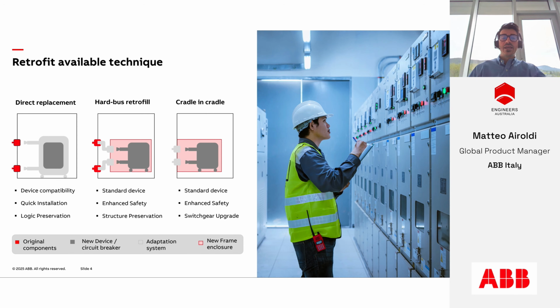The third technique is cradle in cradle. This technique introduces a new frame enclosure inside the cell, allowing the installation of a modern breaker. While it's a valid option for low voltage systems, it is not commonly used for medium voltage applications due to different mechanical and dimensional constraints.